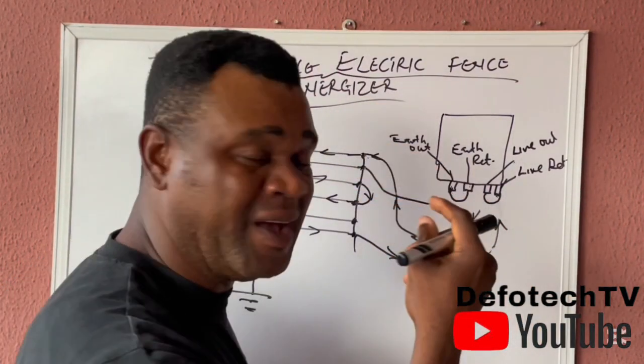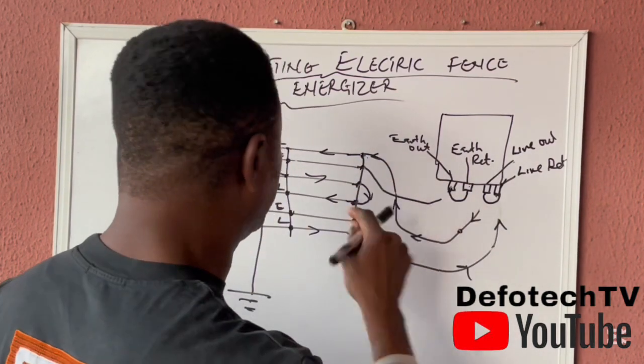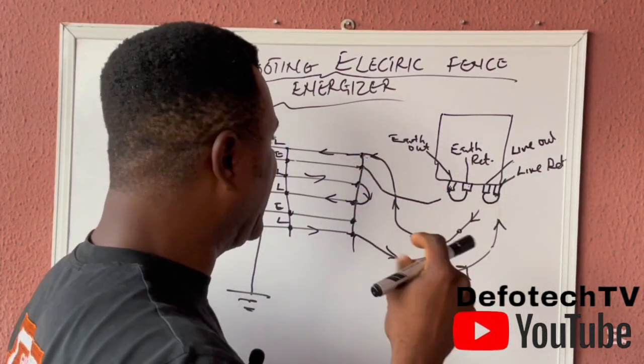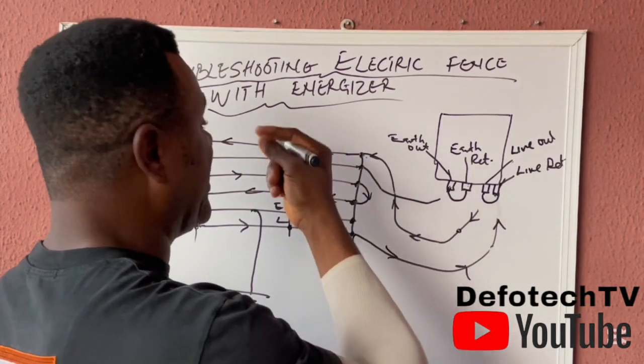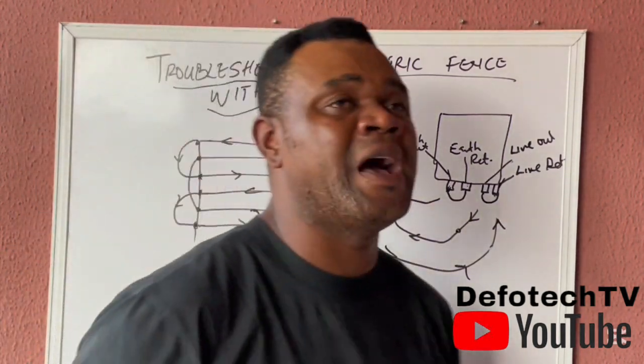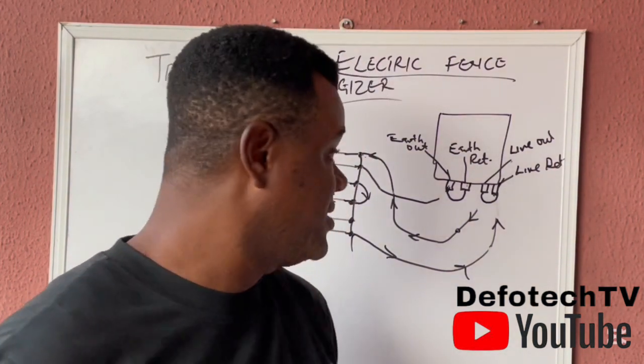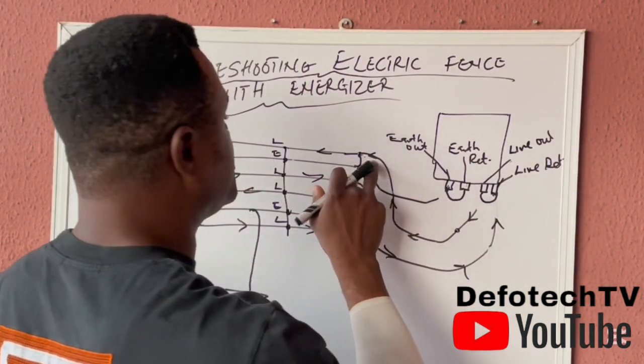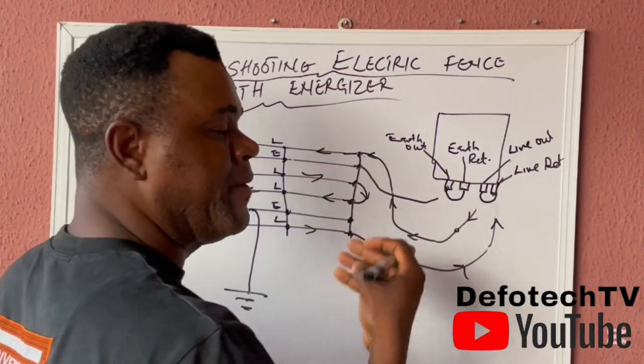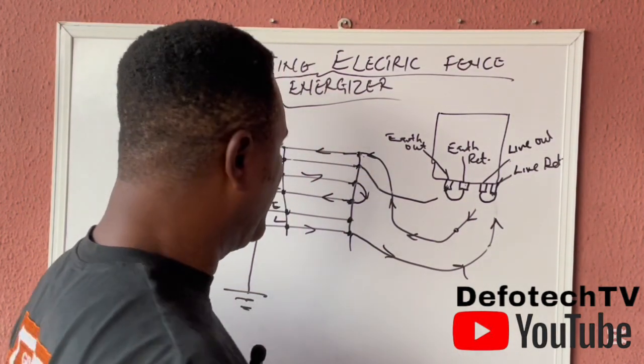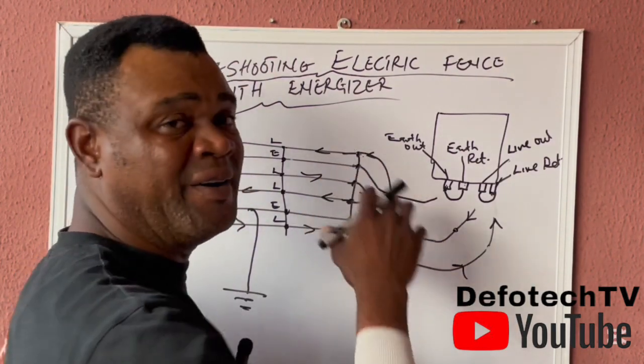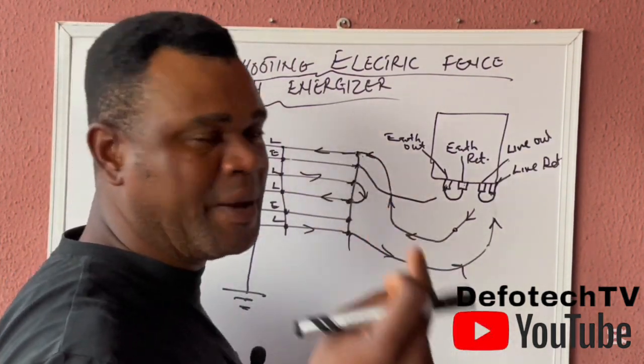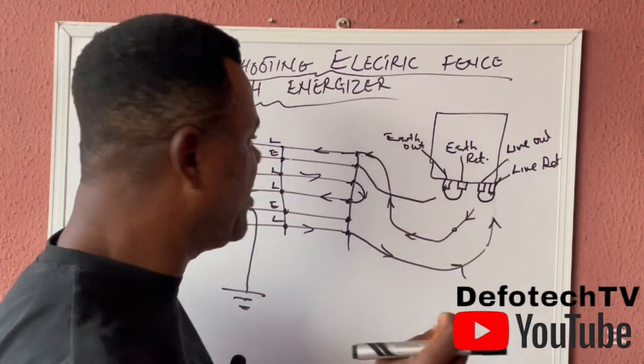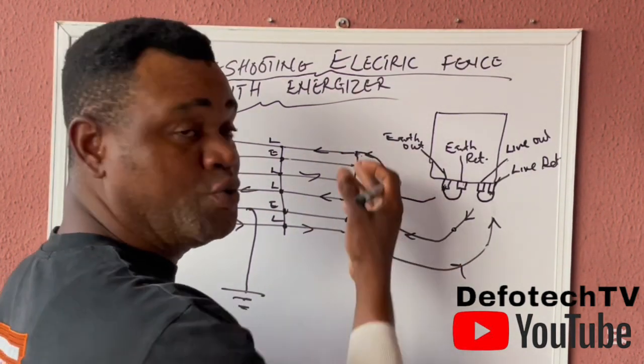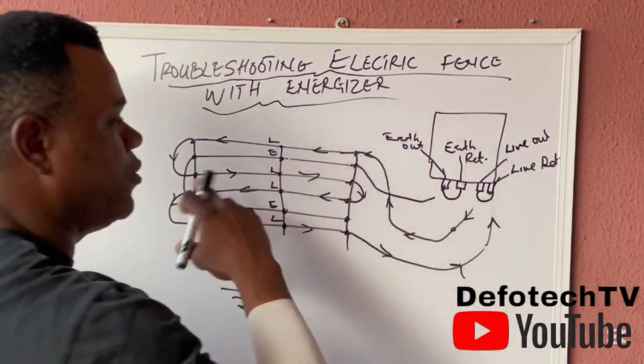if you cannot hear it, it means your fence, maybe somewhere where the fence is terminated, there's, should I say, an open circuit somewhere. It's actually losing somewhere, and sometimes it might be as a result of reactions of cables, or some kind of material you use in linking this with this. With time, you have rainfall, sunshine, and reactions of metals on those terminals. Those terminals may not be that tightened. You see scum has come in and you have partial contact. They're not touching well, so not connecting well. You need to go back to your fence to revisit it.